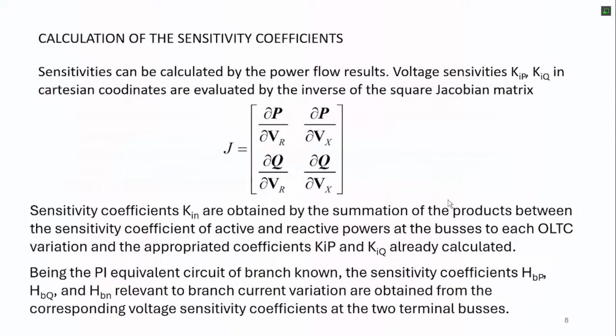Since we have the relationship between voltage and power, by multiplying we can obtain these coefficients for the current too, since the branch parameters are known and we have the voltage sensitivity. The current is the voltage difference divided by the impedance, so once you know the sensitivities with voltage, you can apply them for the current as well. The sensitivity coefficients for the branch current variation are obtained from the corresponding voltage sensitivity coefficients at the two terminal buses.